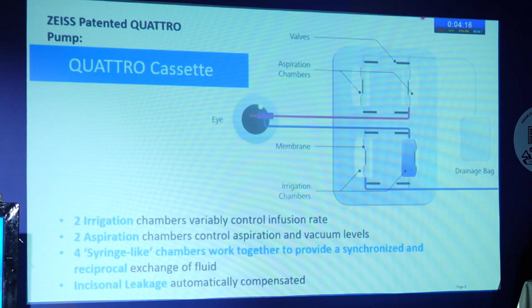Once you go to the cassette, you can also see that there are four chambers, out of which two are irrigation chambers and two are aspiration chambers. These chambers have a membrane, and this membrane is controlled by the air coming in through the pneumatic port. The pneumatic port is connected to the pneumatic pump, which is there inside the machine. There are two pumps, and these pumps receive information from the sensors. If there is a requirement for more fluid to go in or come out of the eye, the amount of air pumped into these membranes is more. Therefore, it increases the speed of the flow, and it also compensates.